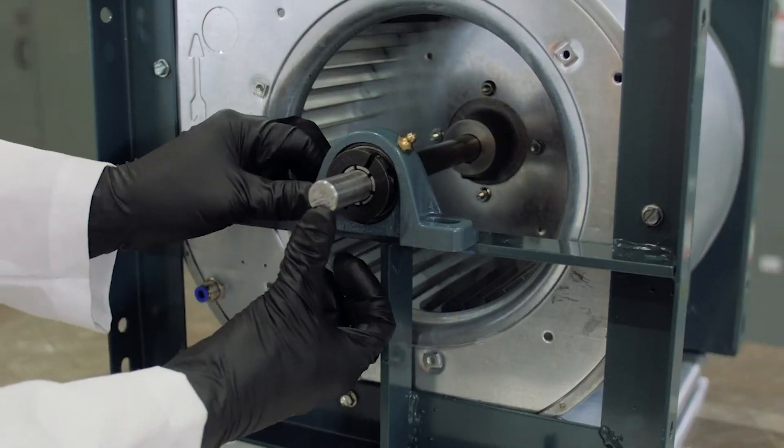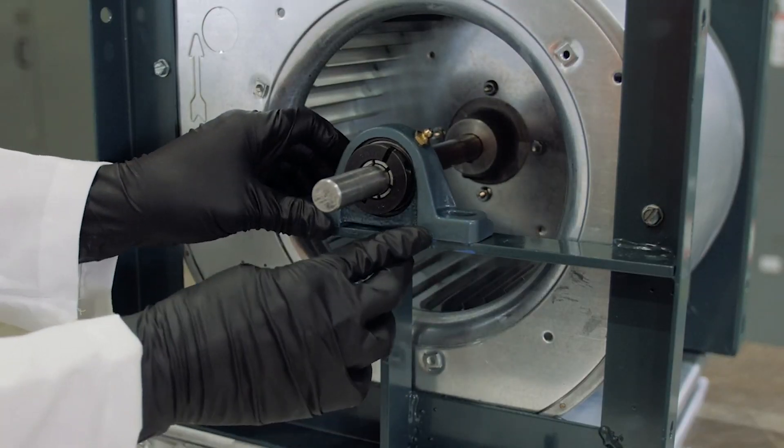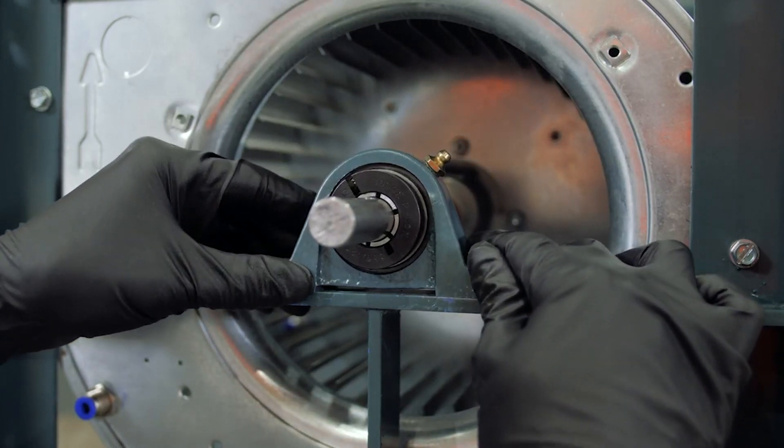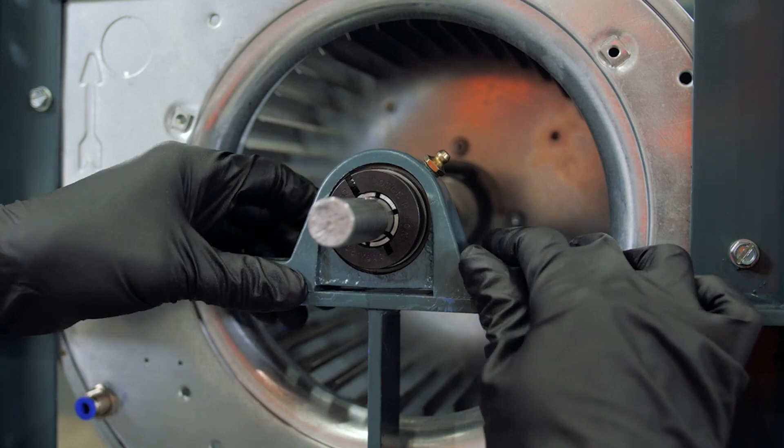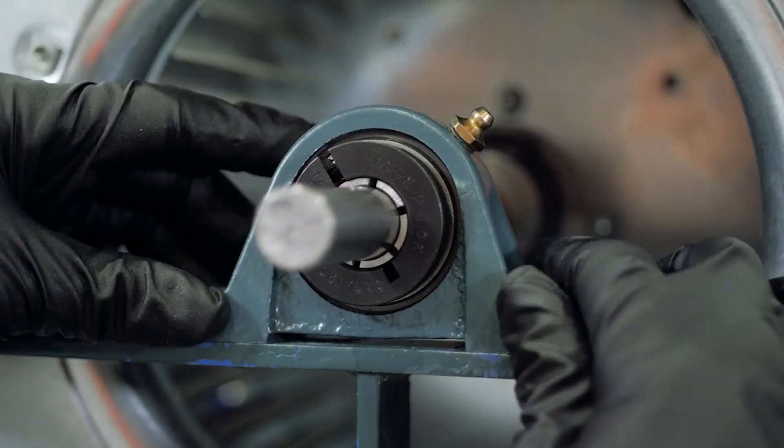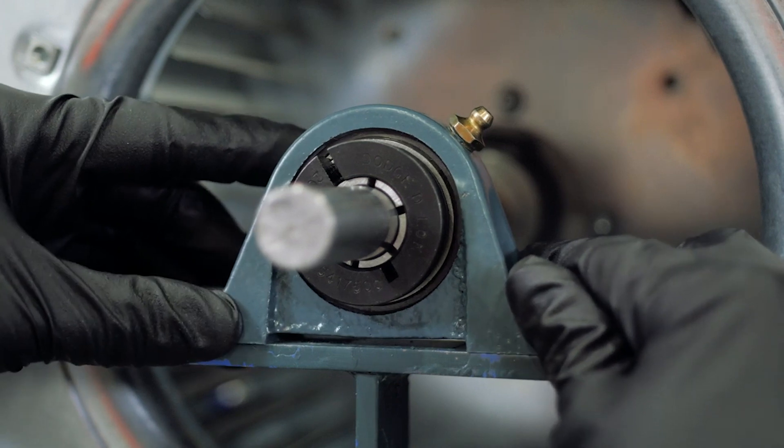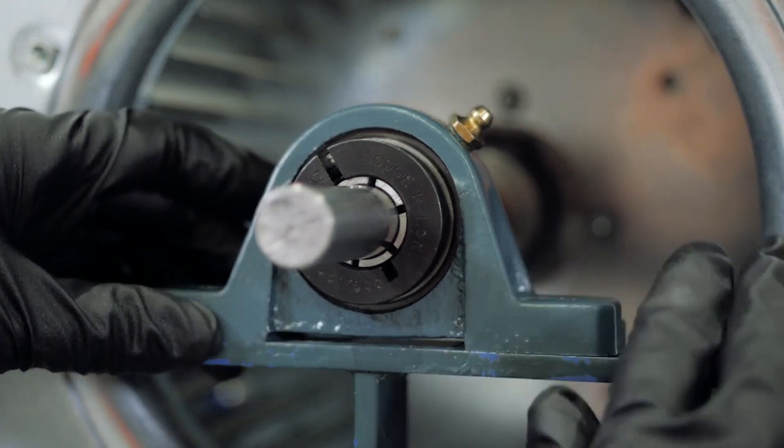Proper alignment is important to maximize the life of the bearing. Dodge ball bearings are rated for plus or minus two degrees of static misalignment. A bearing may be aligned using the shaft to position the insert relative to the housing or by fixing the insert to the shaft and adjusting the housing.